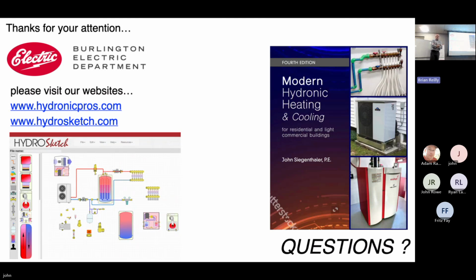But isn't that a good question for SpacePak, the manufacturer? It's an excellent question. They puff up their chests saying, we've been doing this for 10 years. Well, help us with the design. Here's what I've told manufacturers, and actually I'm working with one. I can't tell you who it is right now, but next year you'll probably see something from them. What I feel manufacturers should be doing is providing templates. It's like 10 scenarios, 20 scenarios. Space heating only, space heating plus cooling, space heating, cooling, and domestic hot water, radiant floor versus baseboard. 10 to 20 templates that give you the overall layout.